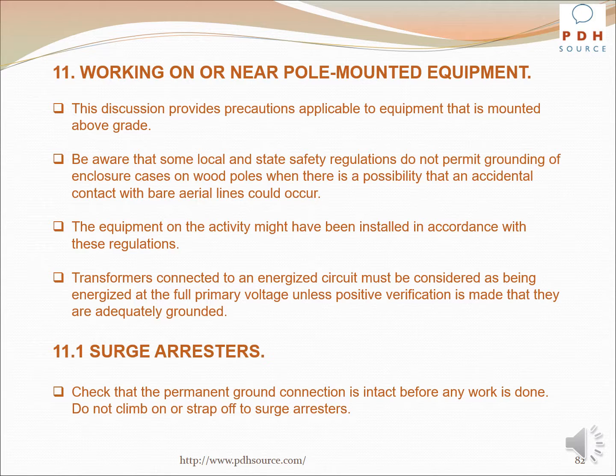Transformers connected to an energized circuit must be considered as being energized at the full primary voltage unless positive verification is made that they are adequately grounded. With regard to surge arresters, check that the permanent ground connection is intact before any work is done. Do not climb on or strap off to surge arresters.